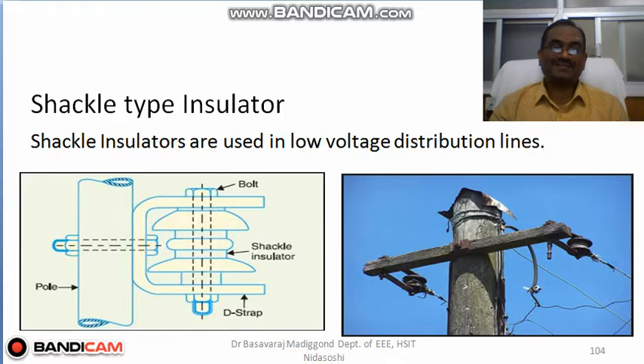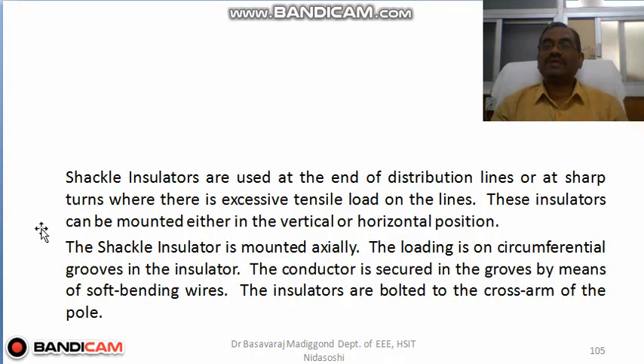Shackle type insulator. This is a Shackle type insulator, and you can see this will be used for dead end poles, where you don't have further conductors to run. So this is a Shackle type. Shackle type insulators are used for low voltage distribution lines. Okay. Shackle type insulators are used at the end of the distribution lines or at sharp turns where there is an excessive tensile load on the transmission lines or distribution lines.